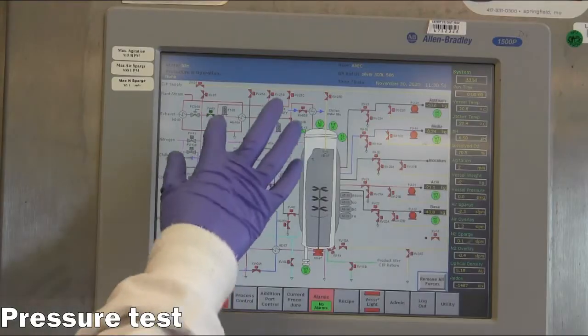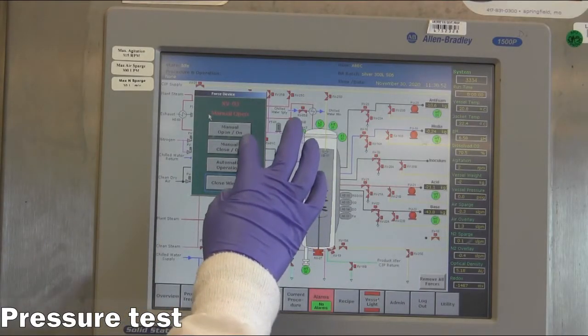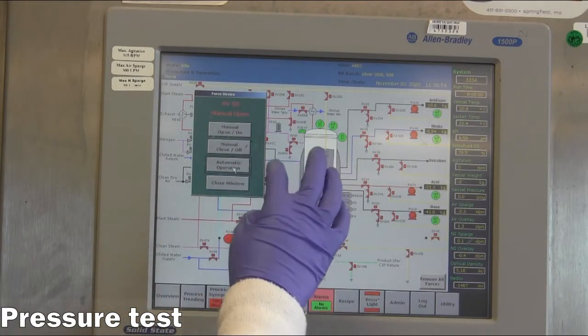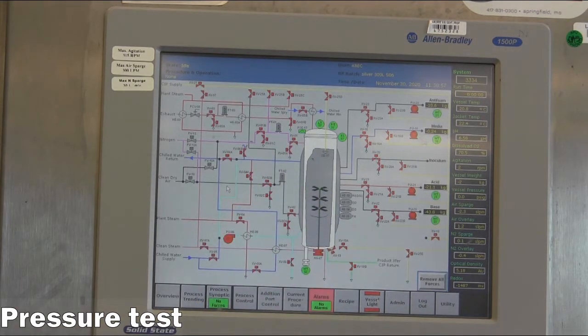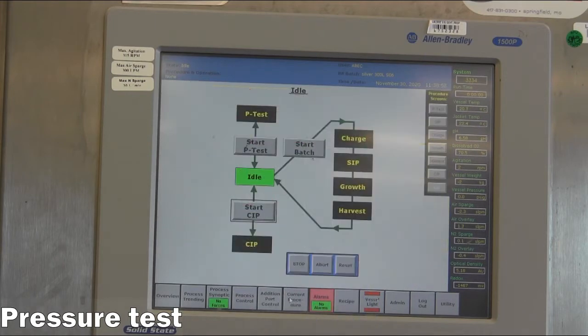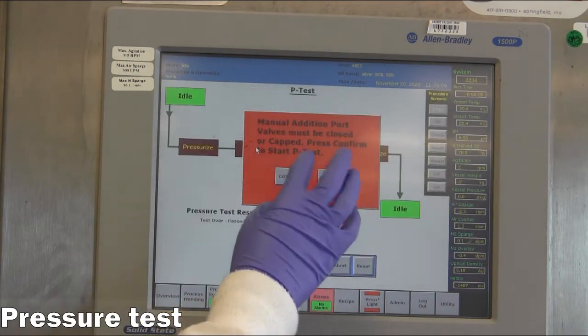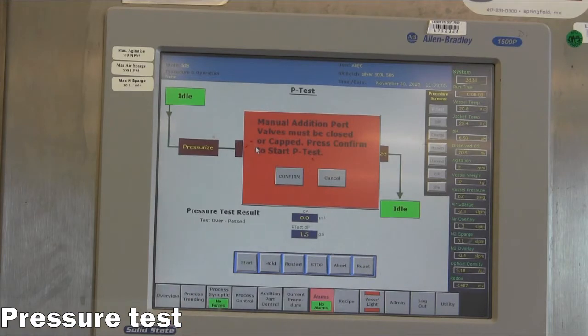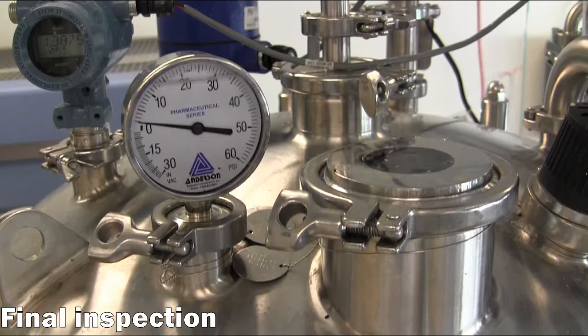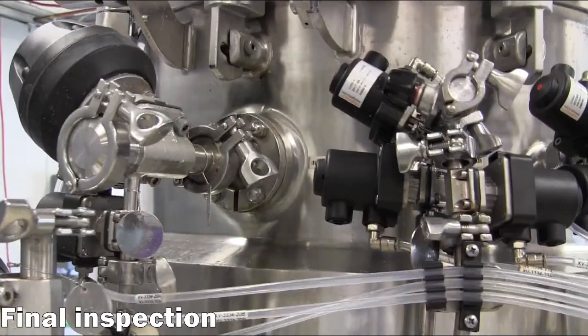To perform a P-test, remove all forces on the process synoptic screen. This sets all valves into a neutral position and allows the reactor controls to open and close valves as required by the procedure. Go to the current procedure window and select Start P-test. A prompt will appear to ensure all addition ports are closed. Use this time to confirm the vessel is sealed, all tri-clamps and hand valves are tightened, and a high pressure sign has been hung up.